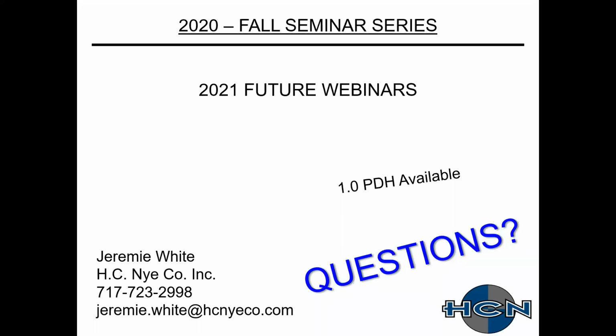Another one: residential style hood, is it comparable to Denlar style hoods? What we did was take our back shelf hood, which is a commercial style hood, and narrow it down to about 2 foot wide. You can go anywhere from 3 foot long up to 8 foot, and it has an integral ECM fan built into it. It's pretty similar to what you'll see with Denlar and GreenFan, or their fire ready hood. Very similar.